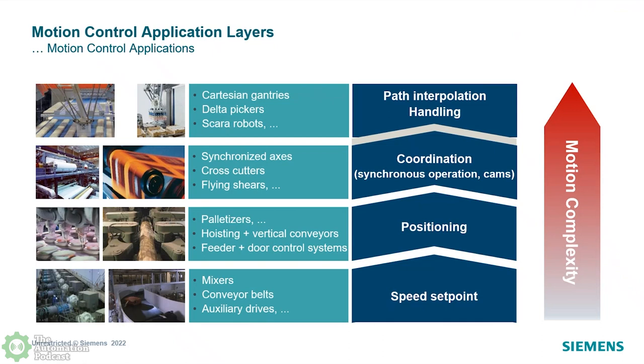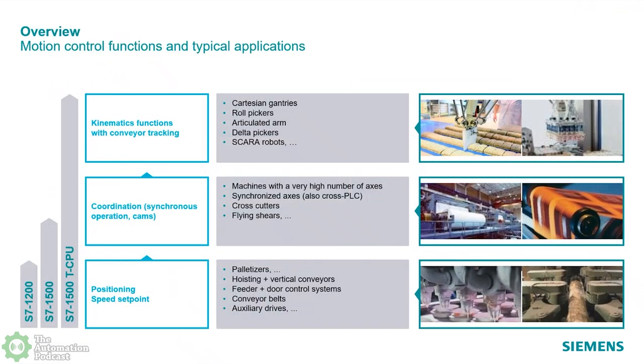Coming back to how Siemens motion controllers fit with all applications: on the left-hand side we have our most popular PLCs — the basic S7-1200, then our S7-1500, and the S7-1500 technology CPUs. What we're showing is how motion complexity builds from simple speed and positioning to coordination to handling applications. Even our simple 1200 basic PLC, very low cost and versatile, can do positioning and speed. The standard 1500 can as well, including fail-safe. The 1500 can also do a little coordination — yes, for simple gearing like 2-to-1, 3-to-1, 4-to-1.